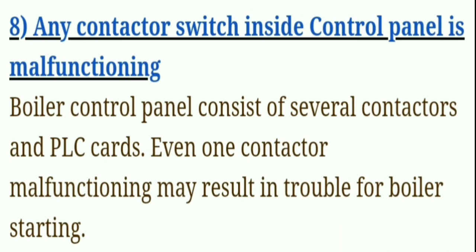Eighth, a contactor switch inside the control panel is malfunctioning. The boiler control panel consists of several contactors and PLC circuits, and even one contactor malfunctioning may result in trouble for boiler starting.